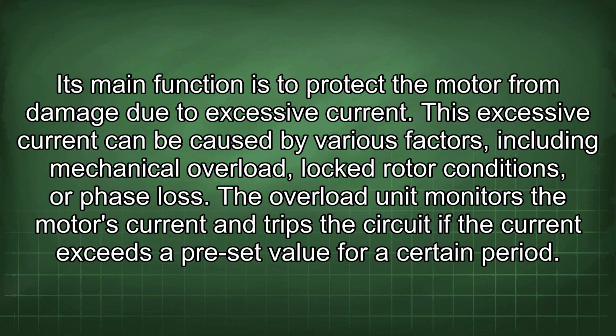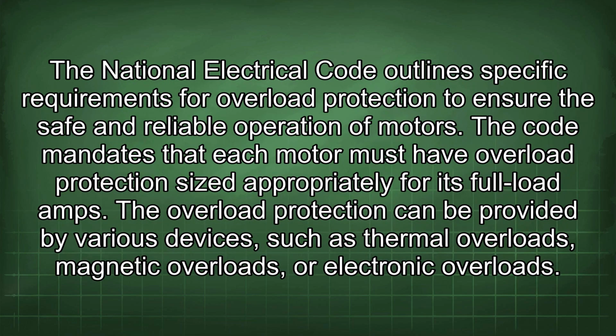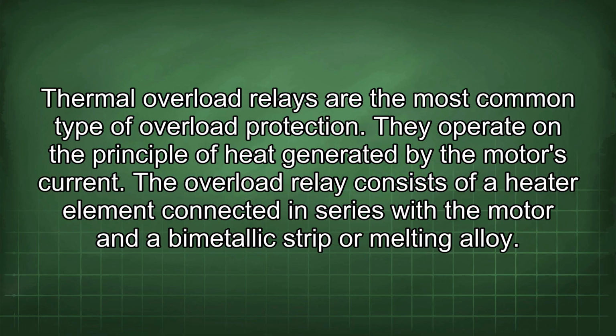The National Electrical Code outlines specific requirements for overload protection to ensure the safe and reliable operation of motors. The code mandates that each motor must have overload protection sized appropriately for its full load amps. The overload protection can be provided by various devices, such as thermal overloads, magnetic overloads, or electronic overloads. Thermal overload relays are the most common type of overload protection.